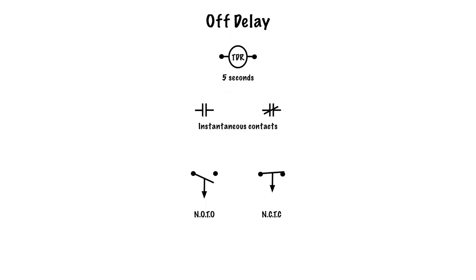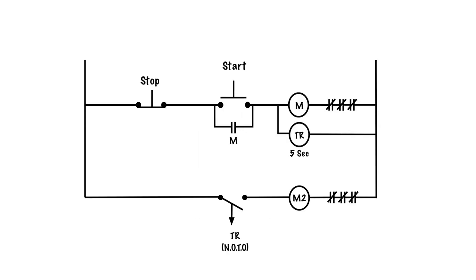After five seconds, the normally open contact opens and the normally closed contact closes — it times out. Now let's take a look at how this plays out in a practical circuit. Here we have a basic start/stop: a stop button, a start button, an M contact, an M coil, an M contact, and then a TDR coil in parallel with M. There are contacts associated with this coil and another motor.